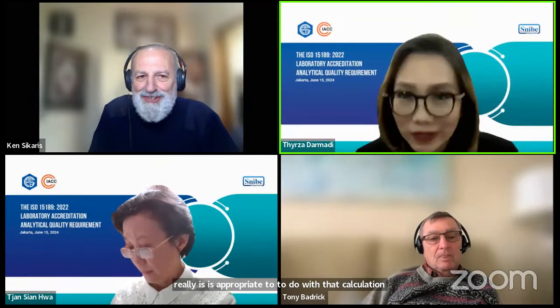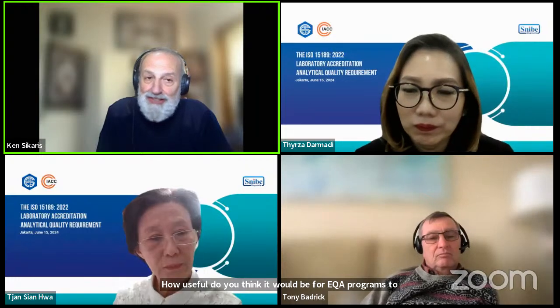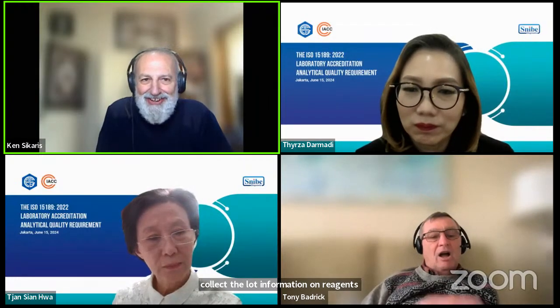Can I ask a question of Tony, because he's a world expert on EQA? The Bio-Rad Unity program does collect the information on the lot of reagent. So there is some information in that internal QC program to be able to differentiate lots. How useful do you think it would be for EQA programs to collect the lot information on reagents rather than just the manufacturer? I think it's critical.